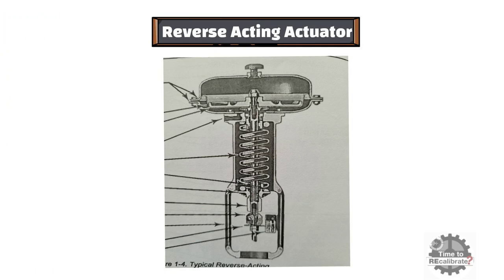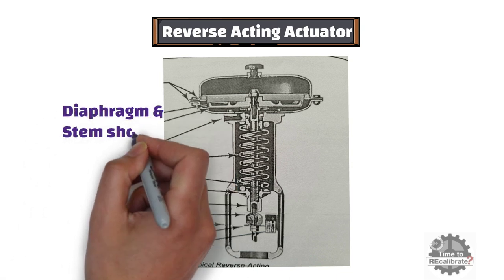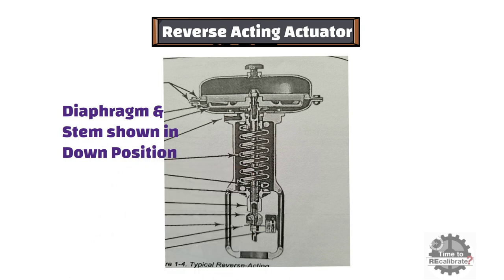As you can see from the picture of Reverse Acting Actuator, all the parts are same as the Direct Acting Actuator except diaphragm and stem. In Reverse Acting Actuator, diaphragm and stem must be in downward position. This is the only difference between Direct Acting Actuator and Reverse Acting Actuator.